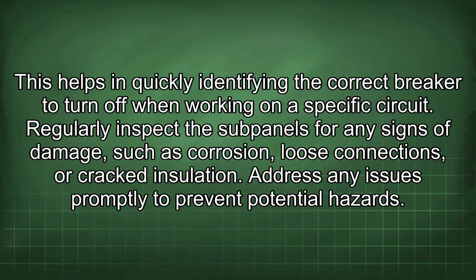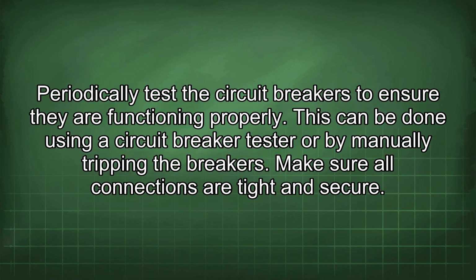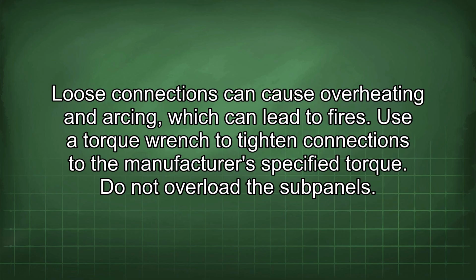Regularly inspect the subpanels for any signs of damage, such as corrosion, loose connections, or cracked insulation. Address any issues promptly to prevent potential hazards. Periodically test the circuit breakers to ensure they are functioning properly. This can be done using a circuit breaker tester or by manually tripping the breakers. Make sure all connections are tight and secure. Loose connections can cause overheating and arcing, which can lead to fires.